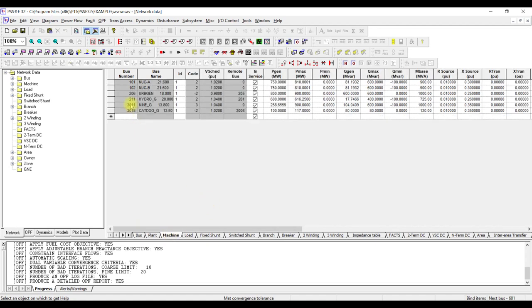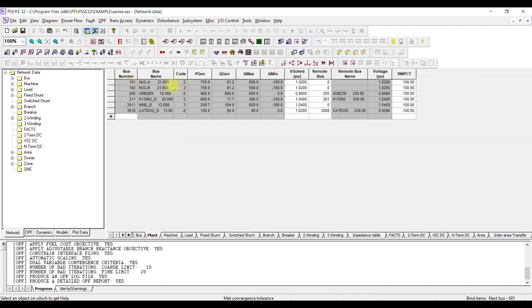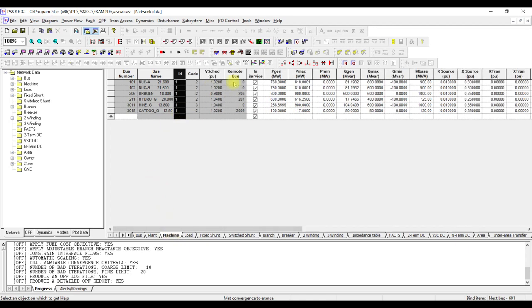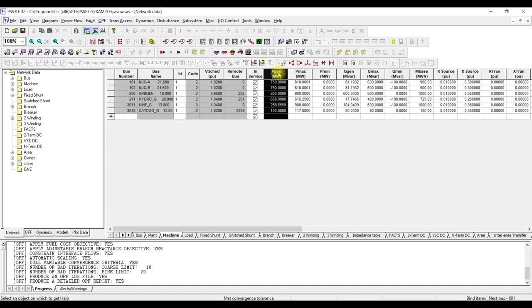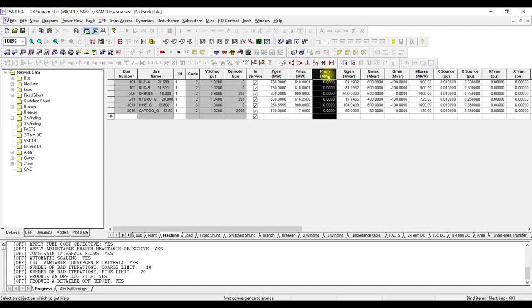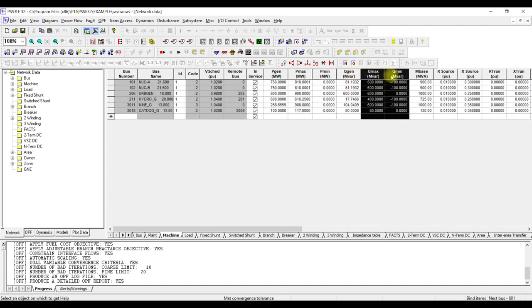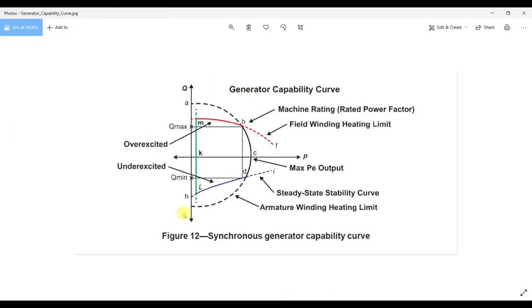Going to the Machine tab: the basic data includes the bus number and the ID, since you can have multiple machines on a certain bus — for instance, a power plant typically has more than one machine, so each machine can be modeled here. For each machine you have different data to model, such as the dispatch, maximum limit, minimum limit, maximum and minimum reactive power. This is the same reactive power capability we discussed earlier — these Q max and Q min values come from the generator capability curve. Even if you do not know the capability curve you can assume some values.